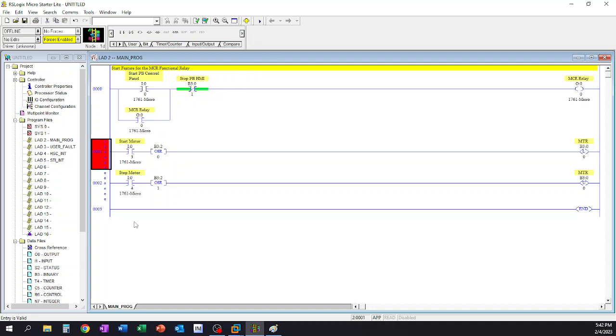So definitely they have their place. I strongly encourage the use of them, but just know when you're using them, how you're using them, and why you're using them for that particular application. If you do, for instance, have a sequencer that's stepping too rapidly or something like that, sometimes putting a one-shot in there can help slow down your sequence so that it's only allowing it to step into that position for whatever reason it would be. And we'll talk a little bit more about sequencing later on, and we might bring back the one-shot for that conversation there.